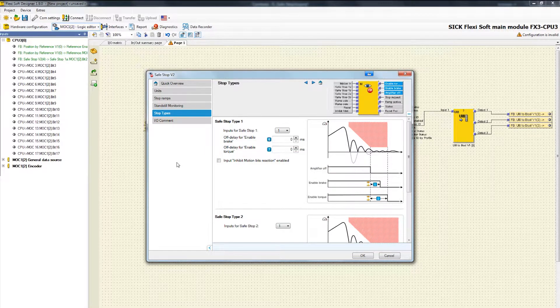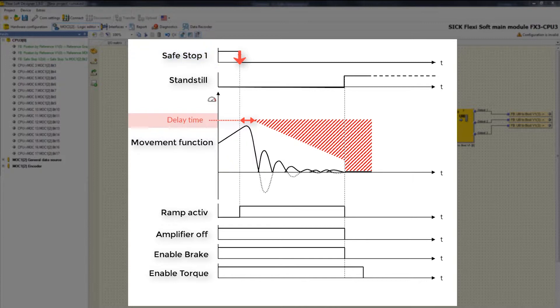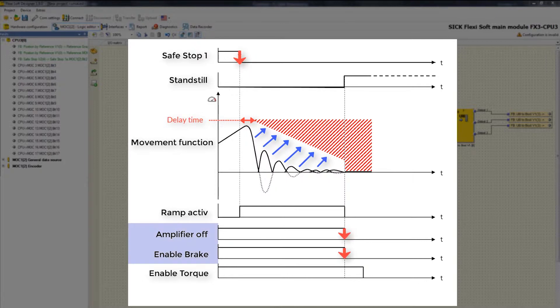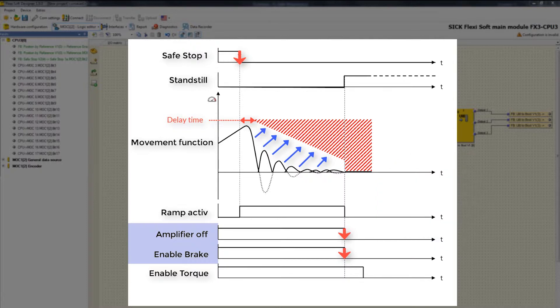In the next tab I will explain the configuration of Safe Stop 1 with the following graphic. When Safe Stop 1 is triggered, the defined delay time until start of the ramp begins. The speed of the drive is decelerated by the machine control and constantly compared with the current speed limit of the stop ramp. After finalizing the stop ramp and reaching standstill speed, the outputs Amplifier Off and Enable Brake go low. At the same time, the safety function Safe Brake Control is activated, which permits the safe control of a holding brake.